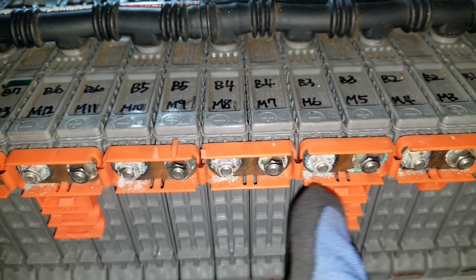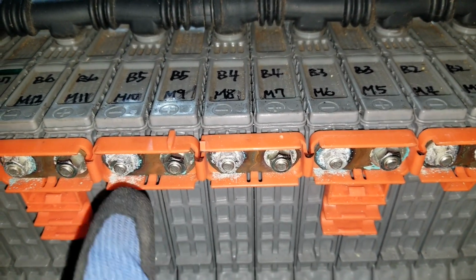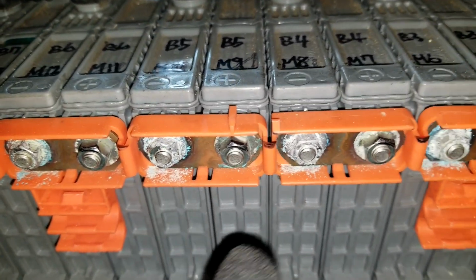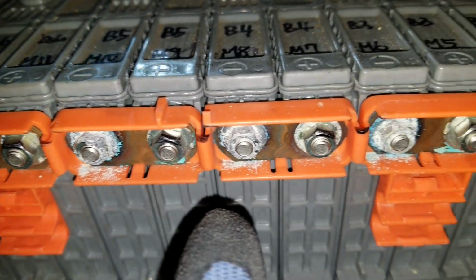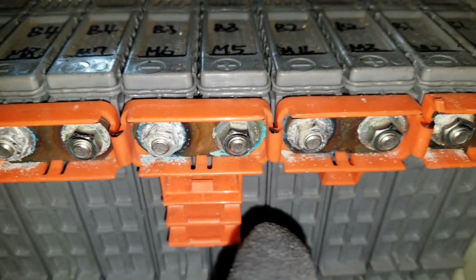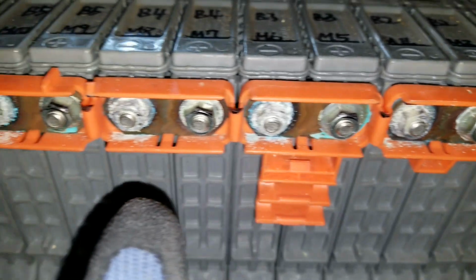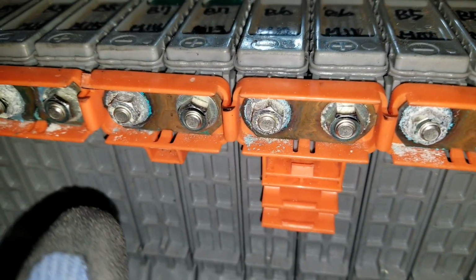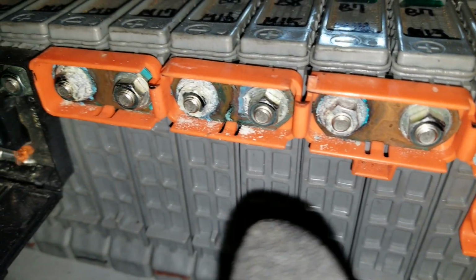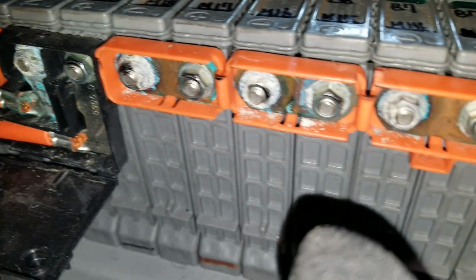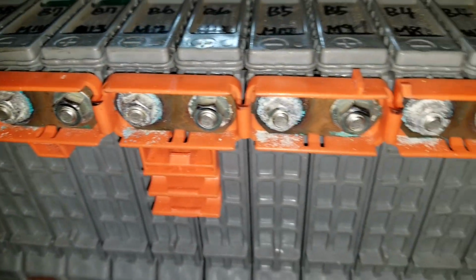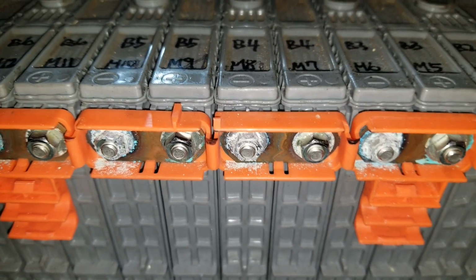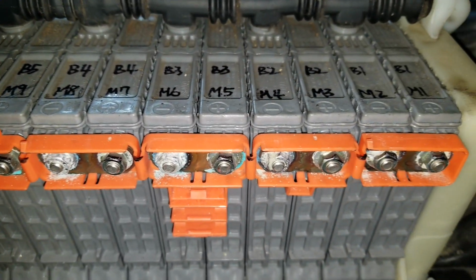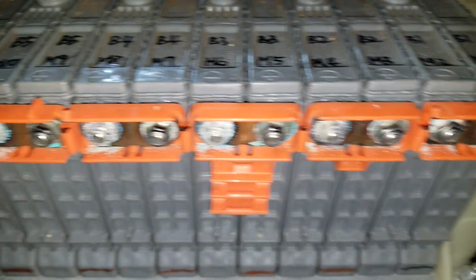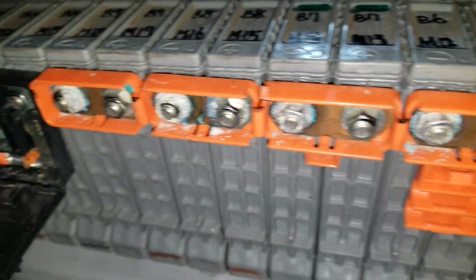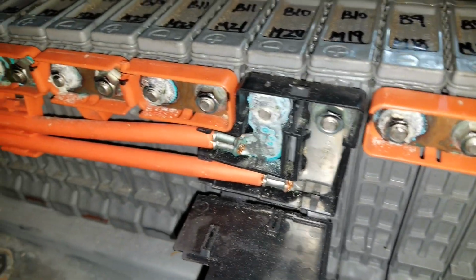So if you have corroded bus bar, it will cause that problem, or corrosion around the nut. You gotta make sure to either clean that or sand it down with a baking soda and vinegar mix. You need to get all that corrosion clean if you don't want to buy a new bus bar with the nut.